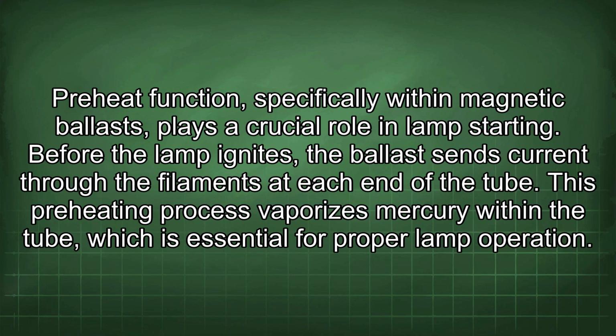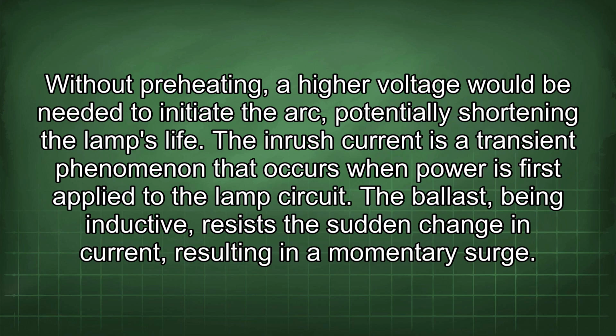The preheat function, specifically within magnetic ballasts, plays a crucial role in lamp starting. Before the lamp ignites, the ballast sends current through the filaments at each end of the tube. This preheating process vaporizes mercury within the tube, which is essential for proper lamp operation. Without preheating, a higher voltage would be needed to initiate the arc, potentially shortening the lamp's life.